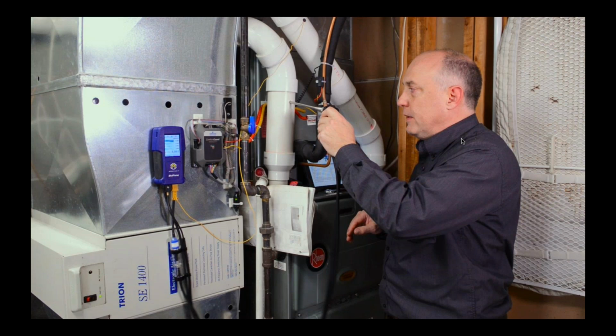Bill Spohn and I were on an expert witness case years ago where an exhaust accelerator was not installed on the flue pipe. An exhaust accelerator means that you have basically a large pipe going out, like that 3-inch pipe I have shown there, but then it reduces down before it goes out to a 2-inch pipe. And what that's for is to eliminate friction in the pipe.